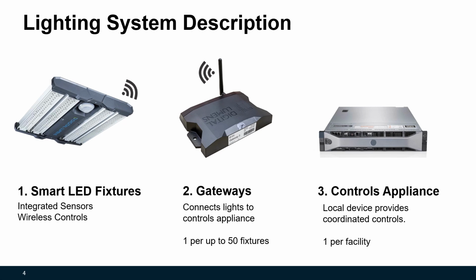The technology involves 3 main components. First, the smart LED fixtures include integrated daylight and occupancy sensors, onboard power metering, and wireless communication. Second, they talk to wireless gateways installed near the ceiling of each zone. These gateways are powered over Ethernet and greatly reduce the amount of control wiring needed in an installation. One gateway can serve up to 50 fixtures. And third, a controls appliance is a local device that coordinates control across all the fixtures within a facility. You can group lights together into zones and control them in tandem. Together, these 3 components allow for granular and flexible controls with very little effort for configuration.